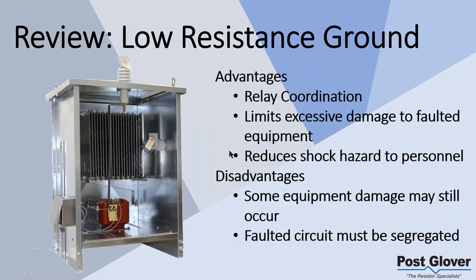We move on to a low resistance ground system. Once again, you hook this up exactly the same way, it's just that the resistance has changed. Now you're at a comparatively lower resistance. IEEE gives some examples for industrial applications: 100 amp let-through current, 200 amp, 400 amp. Those are the common industrial values for let-through current. And just in case we're not clear, let-through current just means the allowed ground fault current that the resistor lets go through. We have this in Ohm's law: V equals IR, voltage equals current times resistance.